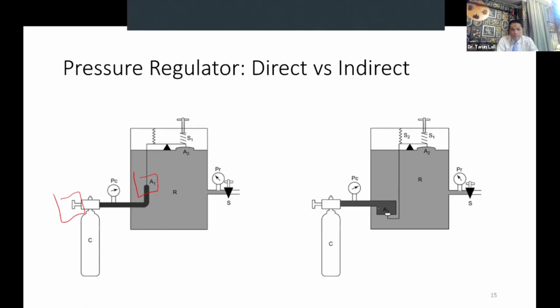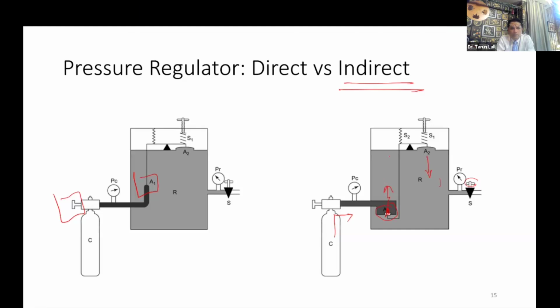So what have they done now as a safety precaution? In this second, the indirect arrangement, they have converted it so that the cylinder pressure, as you can see here, now closes the flow. It stops the flow. And to open the flow, suppose I open the flow, then there is a fall, this will go here. Only then this will move up and start the flows. When I say this, I mean this white thing. And this will move up only when the balance tilts this side, this will go there, and then the flows will start. So by default now, the cylinder pressure is trying to close the regulator flows. So this is what is incorporated in the modern anesthesia machine, an indirect type of pressure regulator.